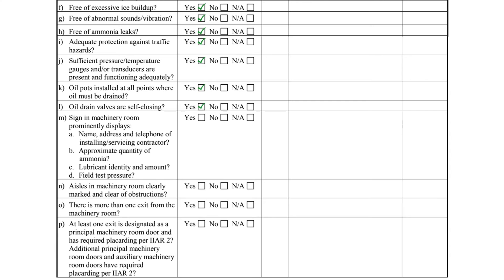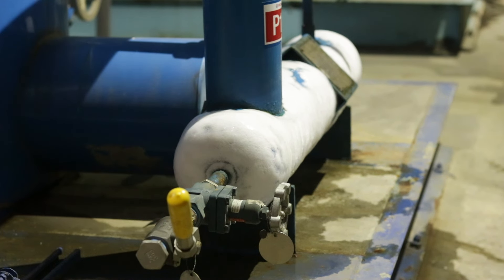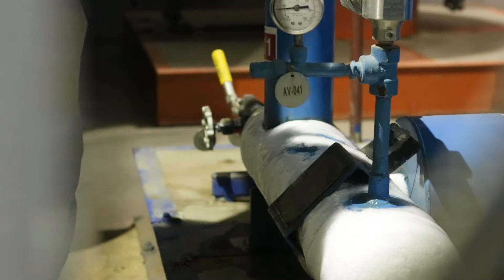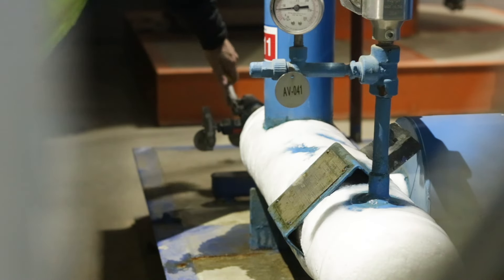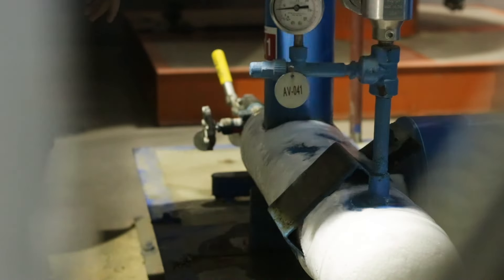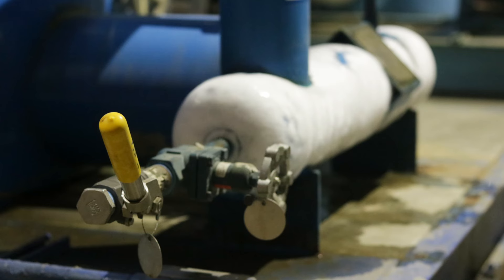Items K and L pertain to oil draining. Item K asks if oil pots have been installed at all points where oil must be drained. Oil pots are not required according to IIAR's design standards, Standard 2, but at minimum, oil drain valves must be self-closing, which is the question asked in Item L.